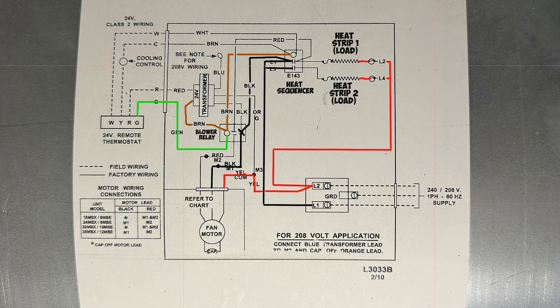And when I put the amp clamp on here, when I put my amp clamp across this heater circuit, when I have voltage to this coil, I should be getting some movement. And the only other reason I wouldn't be getting movement is if these safeties were open or something was open in this circuit. I would still get partial amperage on one of these, unless both of them are open. And if I have the heat on and I got a call and I forced the fan on all the time, not much is going to change just the fan speed because these two contacts right here are just going to switch. If I turn the fan on, but my heat is still calling, the W, if I take away the W, then just the fan is going to run.